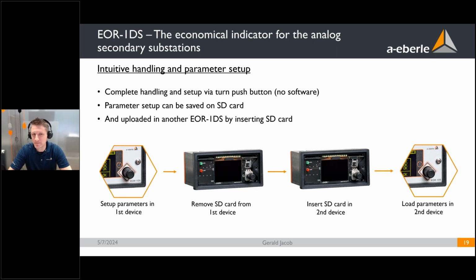This is one possibility. A second possibility that is often used from customers is that you give us your parameter setup, you get a certain specific article number for your device plus parameter setup, and then you can order the device pre-configured with your parameter setup. As an example, our local DSO here around Nuremberg, they order always the same device, but they have 3 different parameter setups, and therefore they have 3 different article numbers that they can order from us directly. So they always get the pre-configured device.